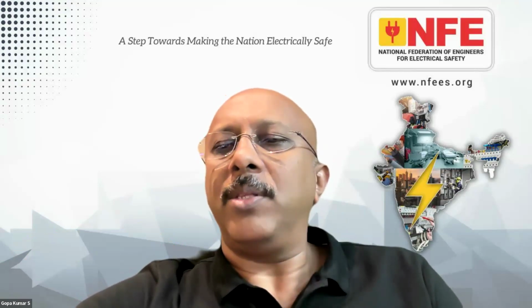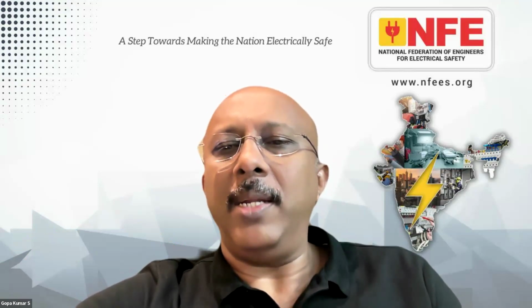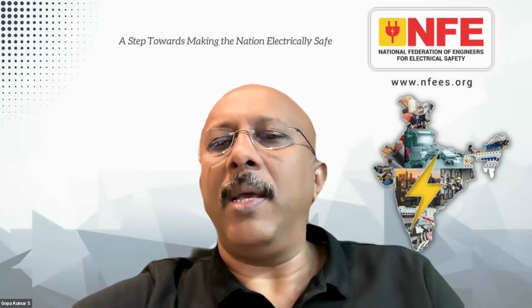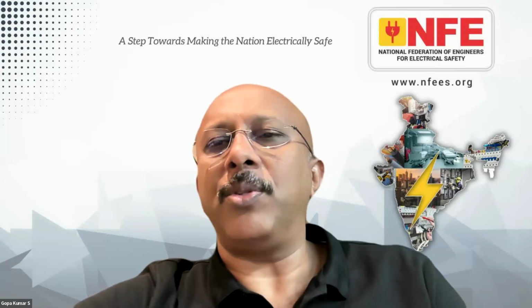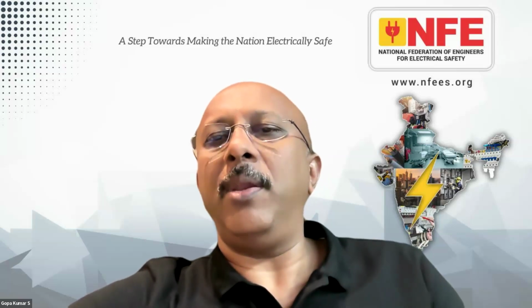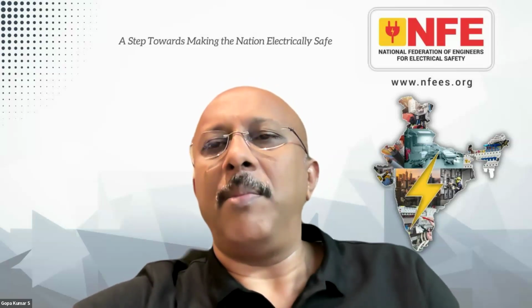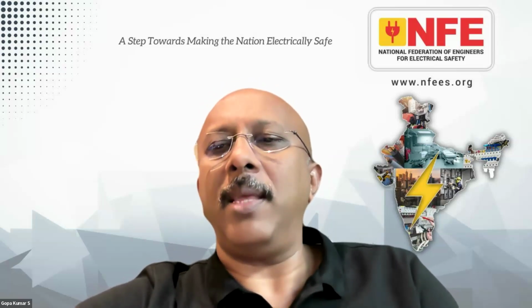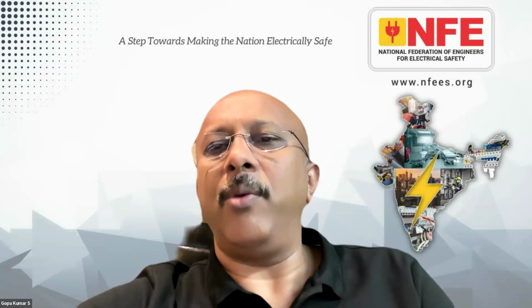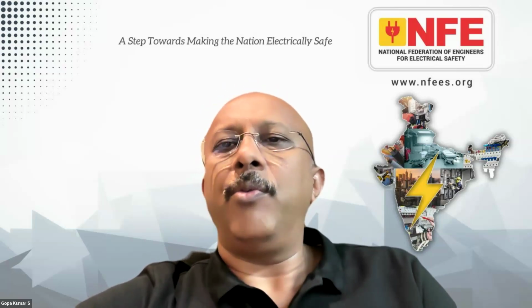The arc flash study and the additional measures are additional measures which can be implemented in an installation which is in compliance with the standard. If the installation is very good, then you make all these things extra. But if you have only these extra things and no basic safety, then you are in trouble. Thank you for the question.